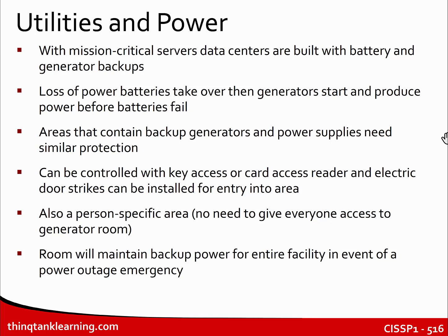The way most enterprise or commercial power systems work is you're running on city power, with power conditioners and power monitors watching it. If that power drops below a certain level, disappears altogether, or becomes dirty, like a brownout, the battery packs will kick in. Those battery packs probably won't last very long, depending on how many batteries you have and how well they're maintained, but they'll kick in, usually just to maintain power. Then there's logic in the backup power system, an automatic transfer switch.